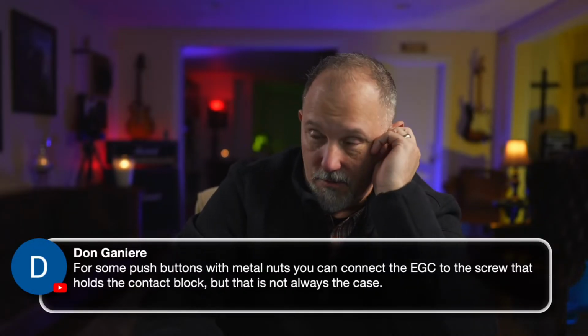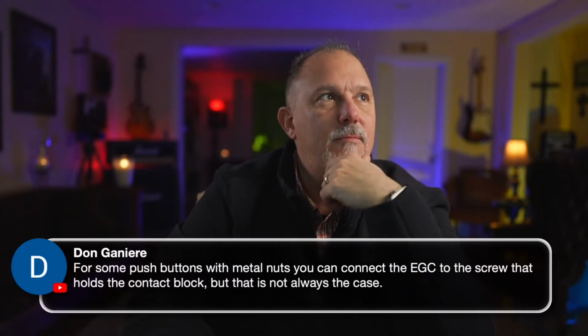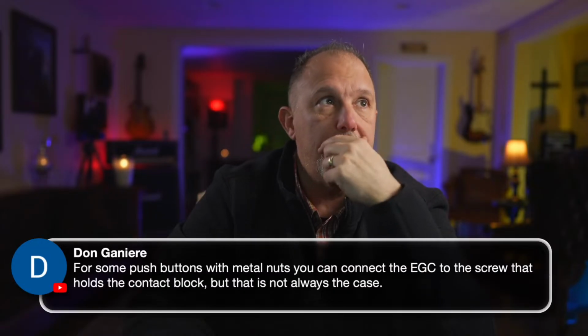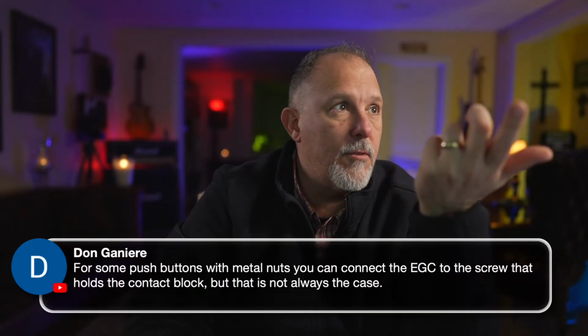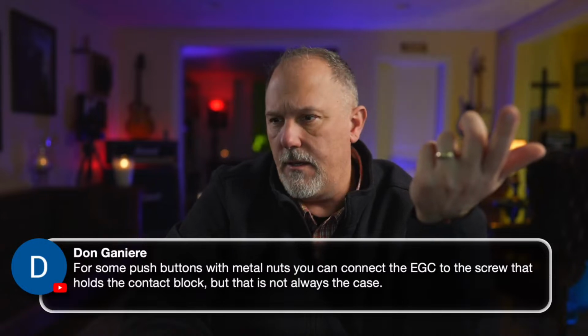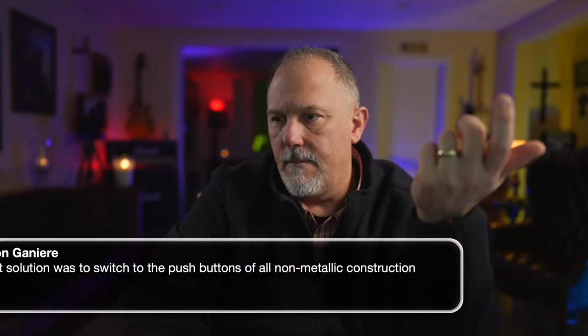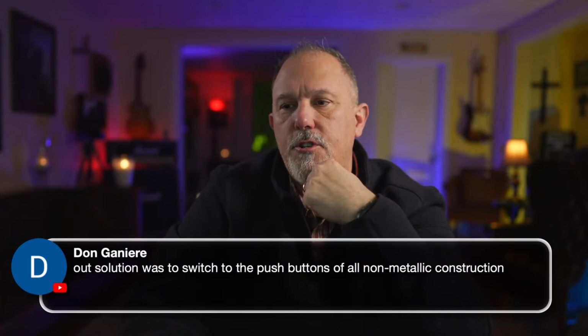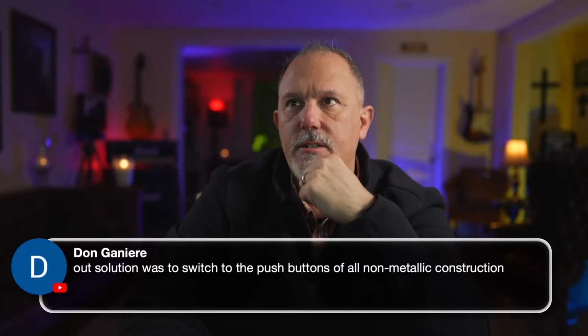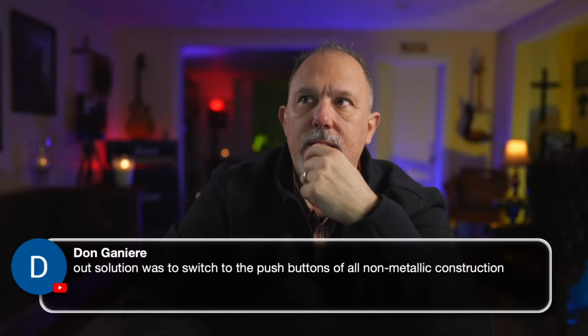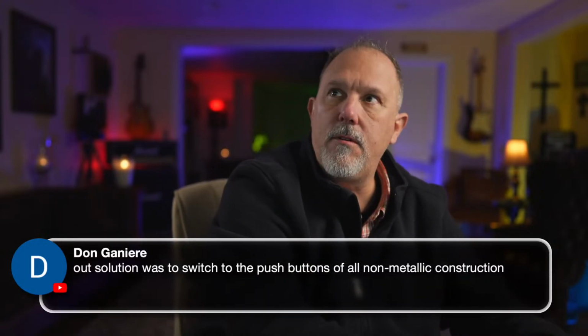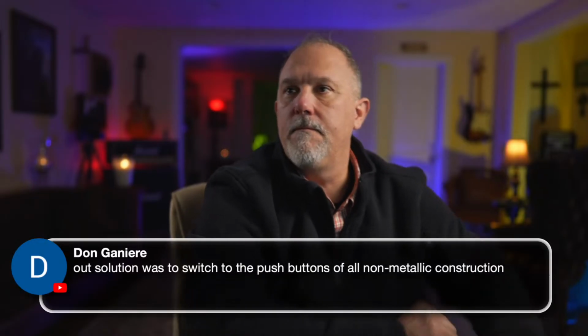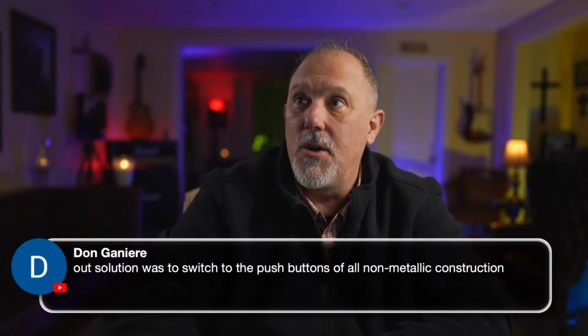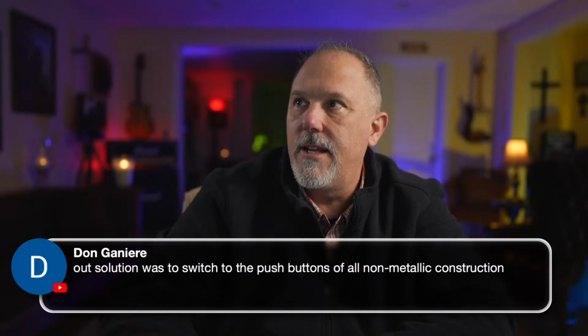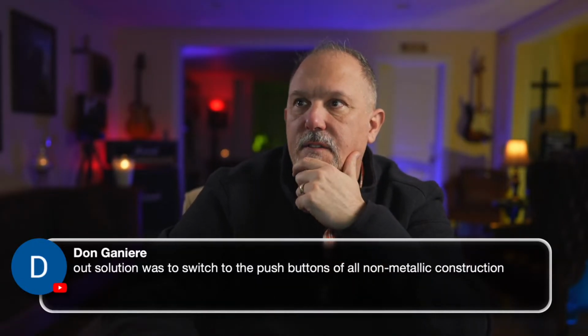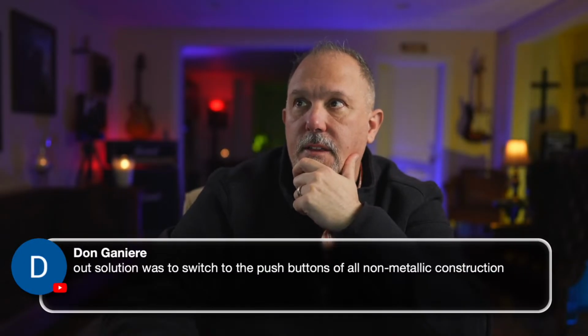that's an interesting. So now what I did was my thought process was I would go to Article 250. Where's my Article 250? I would go to Article 250. Our solution was to switch to the push buttons of all non-metallic construction. Yeah, that's a good question. Metal push button for control. Even the metal ones don't have a terminal. Here's an Allen Bradley. Allen Bradley has a flush head. It's all metal. And there's nothing on there.